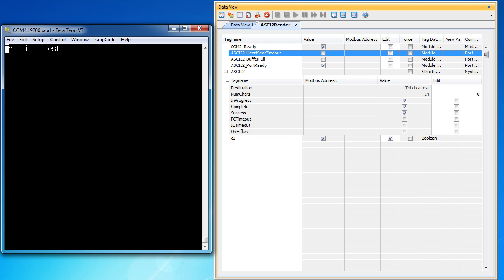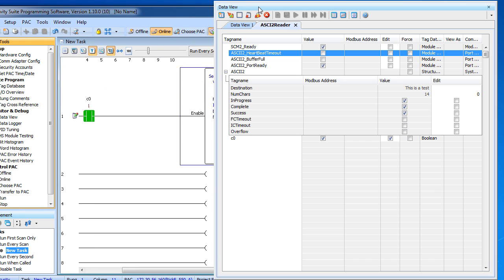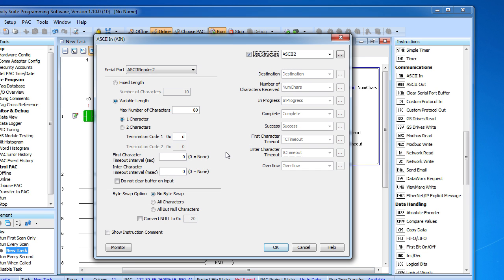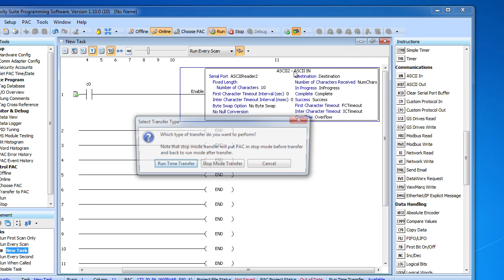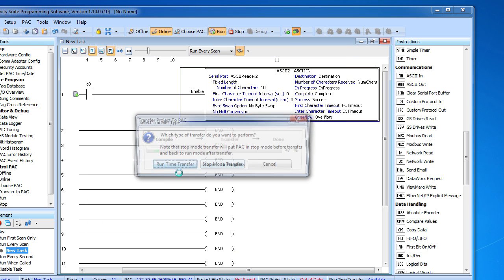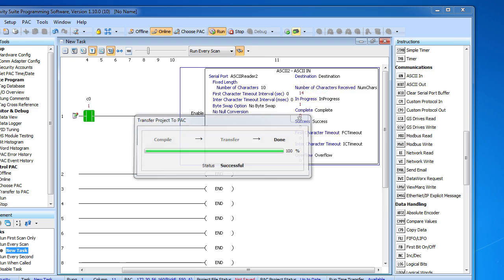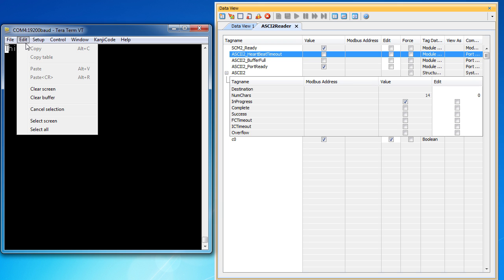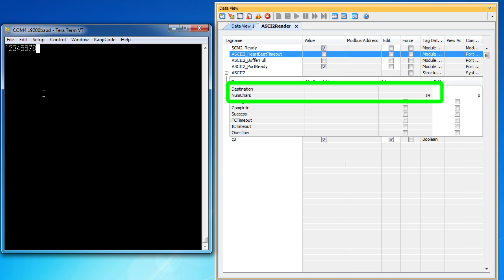Now just for a moment, let's pretend that we have a fixed length string like the one that might come from a barcode scanner. To do that, we just modify the ASCII IN instruction to tell it to expect a fixed length string. We'll use 10 characters for this example. And transfer it to the controller. Let's clear the terminal screen and get rid of this garbage. Now if we type 10 characters, we should see them appear in the destination string when we hit that 10th character. And sure enough we do.